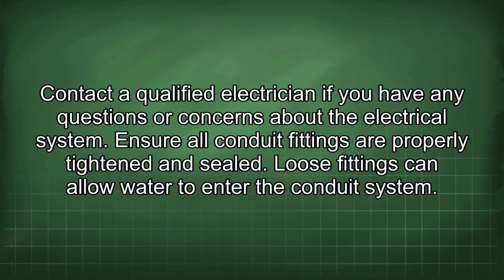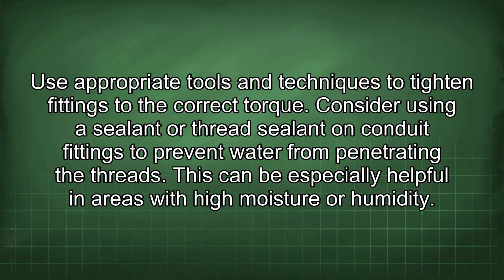Ensure all conduit fittings are properly tightened and sealed. Loose fittings can allow water to enter the conduit system. Use appropriate tools and techniques to tighten fittings to the correct torque. Consider using a sealant or thread sealant on conduit fittings to prevent water from penetrating the threads. This can be especially helpful in areas with high moisture or humidity.